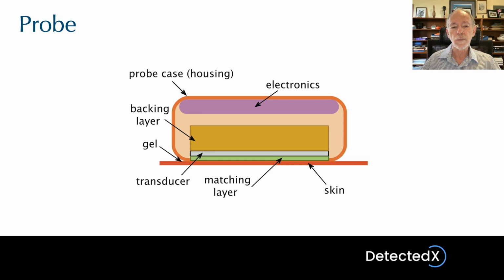Now when the transducer vibrates, it can transmit energy into the patient's tissues, but equally into the body of the probe. We don't want transmitted ultrasound in the body of the probe because that could reflect around and create echoes that the machine would think had come from the patient's tissues. So the backing layer that I've shown here is simply there to absorb energy that would otherwise be transmitted into the body of the probe. The other thing that I'm showing in this diagram is the electronics in the probe. This, as we'll see later on, is used to select different parts of the transducer to operate as transmitter and receiver at various times.